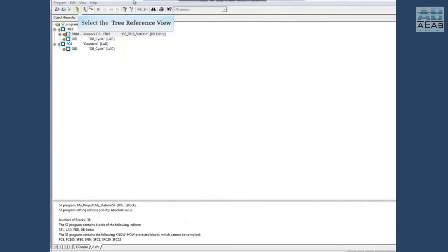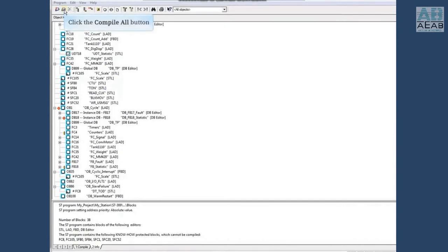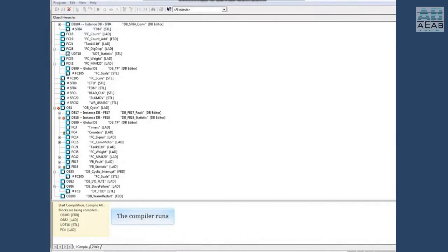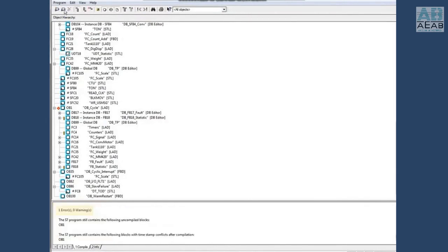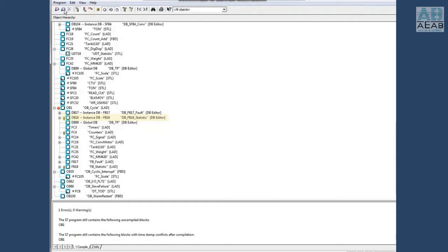Let's go back to the tree reference view. We will now compile all the blocks and see if it fixes all the interfaces. Click the compile all button. The compiler runs and indicates there's an error. OB1 could not be compiled and it still contains the timestamp conflict. The red X is gone next to DB18 but there are still yellow exclamation points next to DB18, FC4, and FB18, all being called from OB1. Close the check block consistency window.